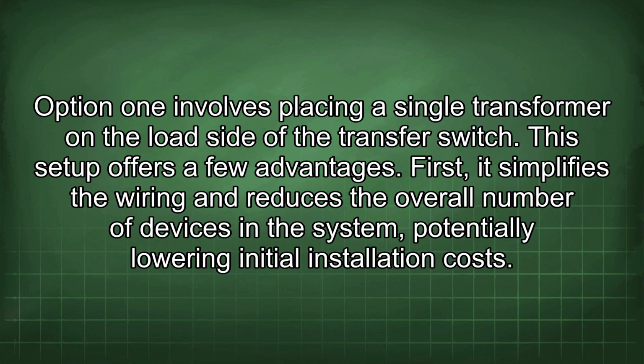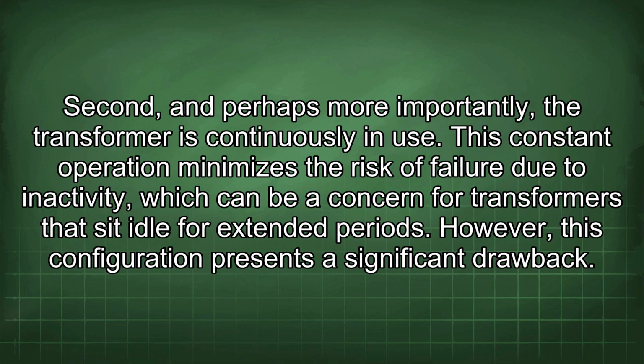First, it simplifies the wiring and reduces the overall number of devices in the system, potentially lowering initial installation costs. Second, and perhaps more importantly, the transformer is continuously in use. This constant operation minimizes the risk of failure due to inactivity, which can be a concern for transformers that sit idle for extended periods. However, this configuration presents a significant drawback.